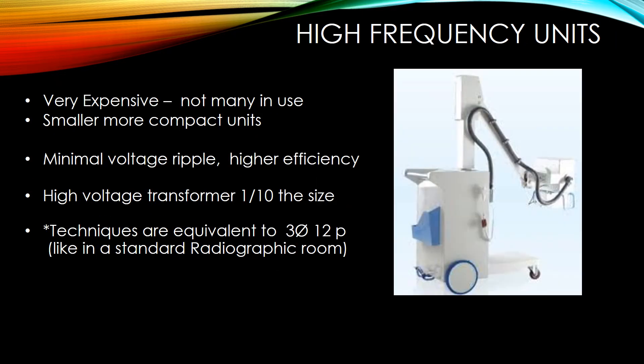High frequency units are very expensive and not many are in use. They are smaller and more compact with minimal voltage ripple and higher efficiency. They use a high voltage transformer and techniques are usually three-phase, similar to a standard x-ray room.